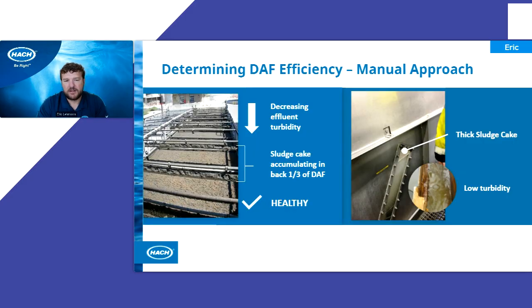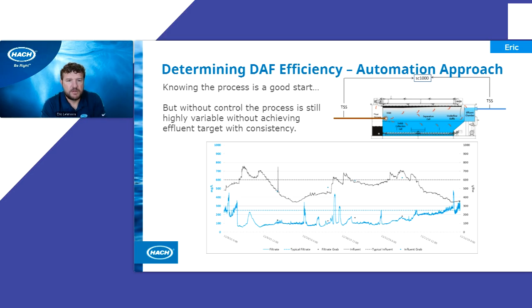Maybe there's a manual approach or visual management, where they're just visually looking at the effluent quality. The back 1/3 of the DAF is where it should be accumulating that sludge cake, and really visually seeing, hey, this is healthy or it's not, meaning that maybe we need to increase our chemical dosing or decrease it.